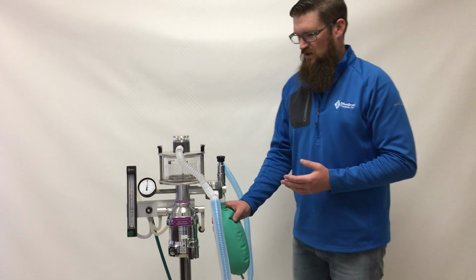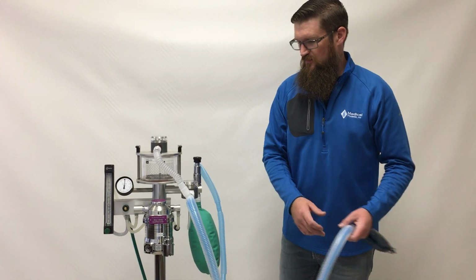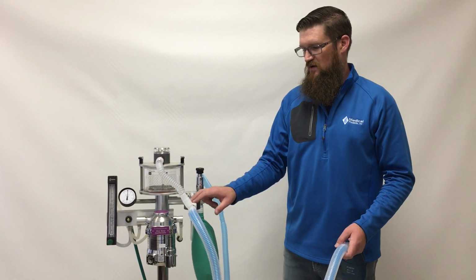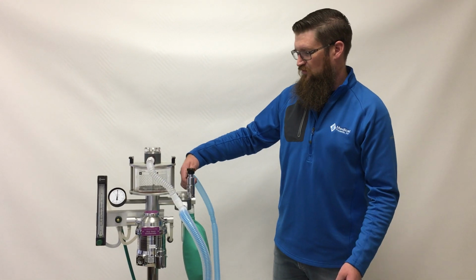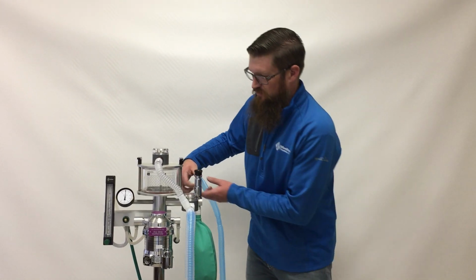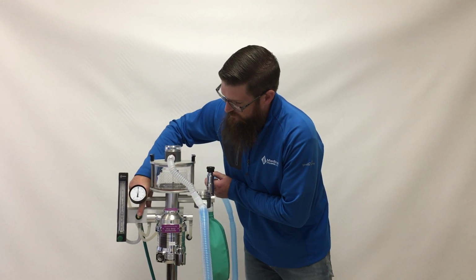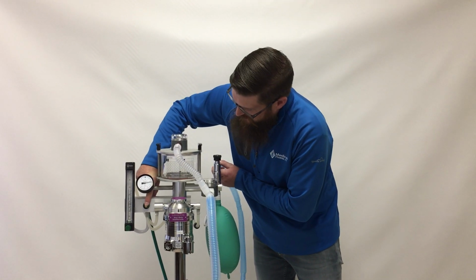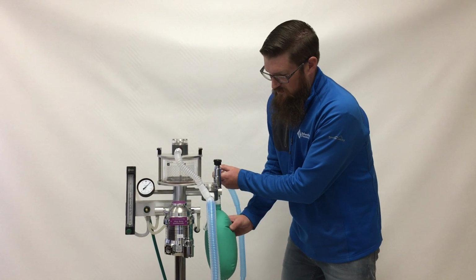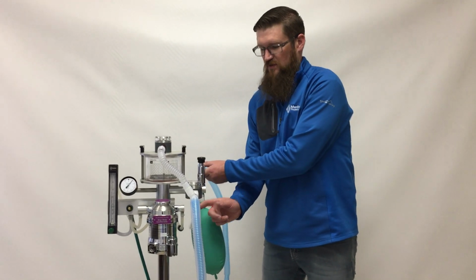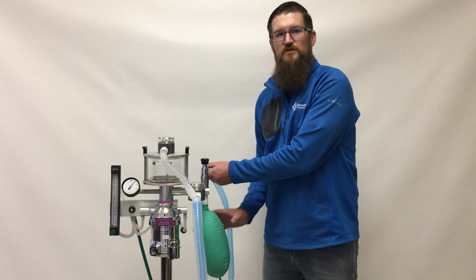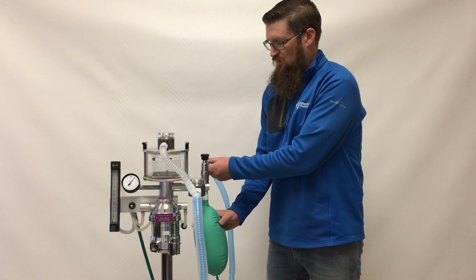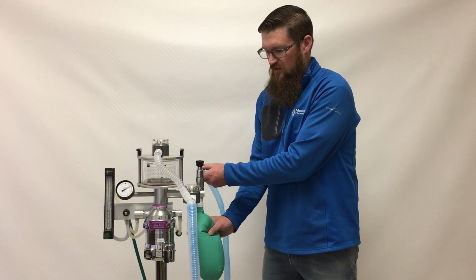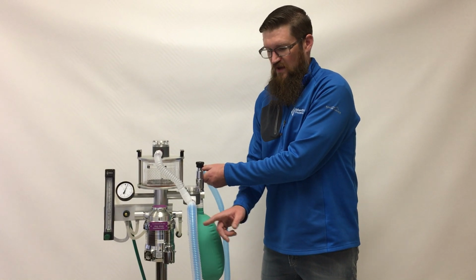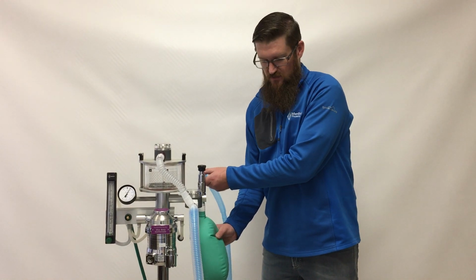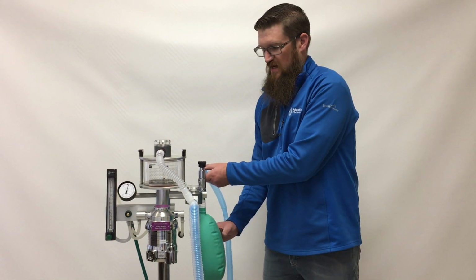One of the questions that we get a lot, which is a very good question, is manual resuscitation using the safety relief valve. If you hold the occlusion valve and you want to manually resuscitate the patient, I'm just going to build up a little bit of pressure here with the flush. You can still do that. The valve is not big enough to relieve all the pressure in the circuit, so it will still allow the circuit to build up plenty of pressure. If you want to hold the occlusion valve and give a breath, some gas will escape through the valve, but not enough to prevent the delivery of the breath to the patient.